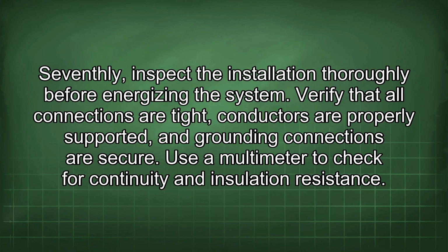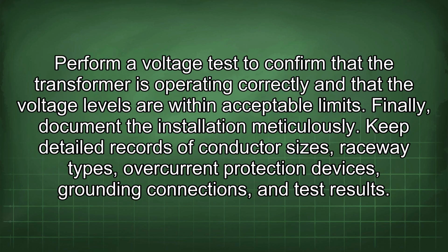Seventhly, inspect the installation thoroughly before energizing the system. Verify that all connections are tight, conductors are properly supported, and grounding connections are secure. Use a multimeter to check for continuity and insulation resistance. Perform a voltage test to confirm that the transformer is operating correctly and that the voltage levels are within acceptable limits.